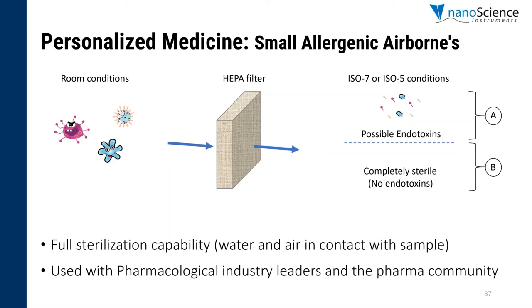Meanwhile, advanced applications in the pharmaceutical area require complete sterile conditions during sample development. Because of this requirement, we offer the capability of sterilizing the whole unit and maintaining ISO 7 or ISO 5 conditions simultaneously. This includes sterilizing the water and even the air used for sample development. Typical environmental conditions use water and room air to obtain your desired temperature and relative humidity. This conditioned air, with your set points, goes directly through a HEPA filter to remove any microorganism or dust before it enters the chamber of the unit. By completely sterilizing the water lines and the airflow path, we establish a sterile environment free of possible endotoxins while maintaining ISO 7 or ISO 5 conditions.